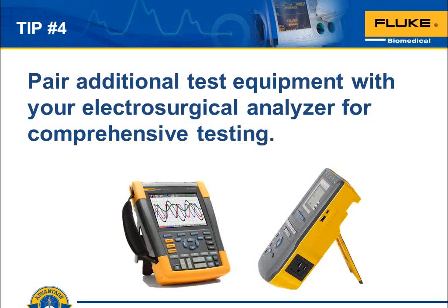If the ESU includes an argon gas envelope capability, the gas flow and pressure should also be tested. So you're going to want a gas flow analyzer, and that's the right test instrument to use for that. So you've got at least 3 pieces of test equipment you probably ought to be seriously considering using, and do a real thorough inspection. You're only going to be looking at these things twice per year. Think about how many surgeries are going to be going on, how much those devices are going to be used in between each inspection, and I think you'll get the idea.